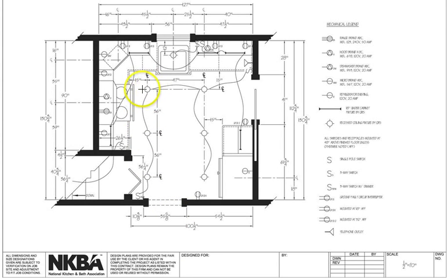So if we start here with this recessed light, we can see that it is 15 inches off of the counter to the center. And if we look over here, we'll see the dimension 15 inches off of this counter to the center. These light fixtures are 47 inches apart, 36 inches apart, and 36 inches apart. Lastly, you will see, again located on the right, the mechanical legend as well as any notes would be located there.